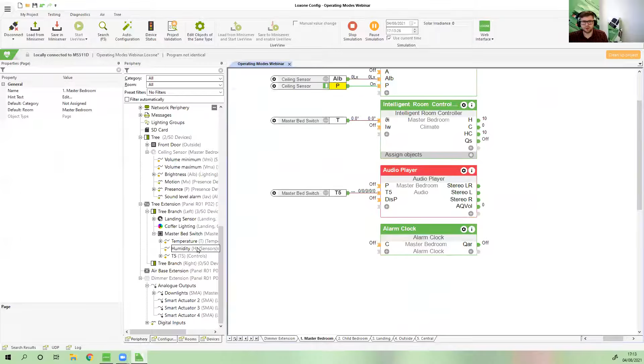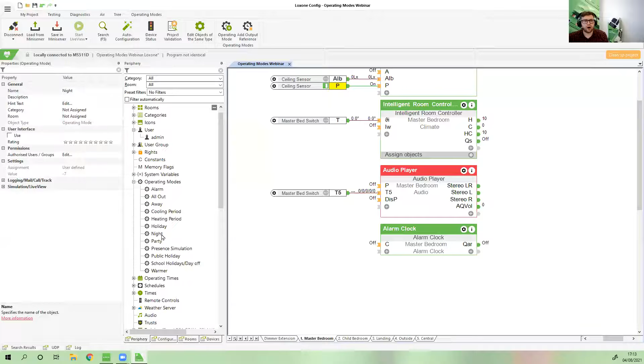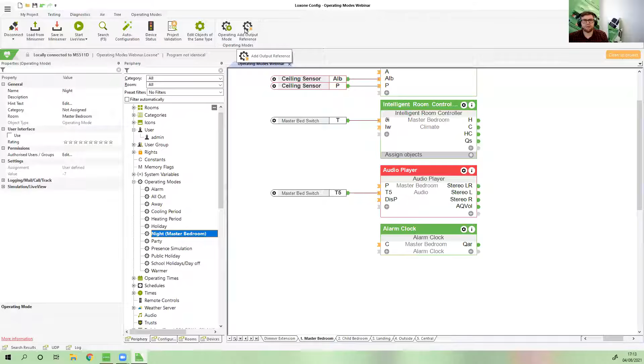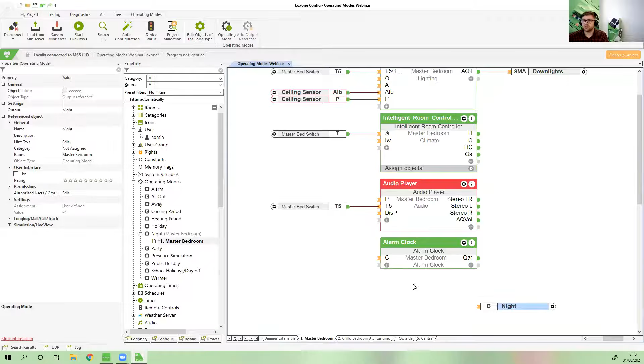So the very first thing we can do there is go back into our lighting controller, go into the automatic tab, and we could create a new rule that says that if the active operating mode is night, I want to go to the night mood on motion. Simple. So now, if we simulate this, it's currently not night mode because night mode is not active. We trigger the presence sensor and we go to bright. However, if somebody triple clicks in the bedroom, look at this, night mode is now on. And then if we trigger presence, we now go to the night mood, which is 20% brightness. Boom. So there's the first instance of an operating mode working.